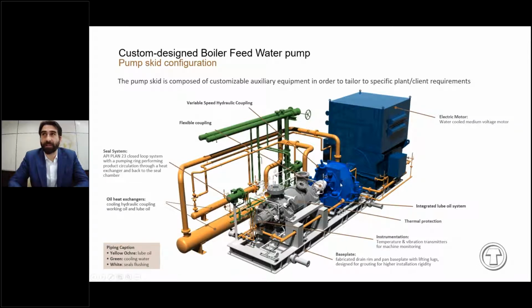It has an integrated lube oil system. You can see in orange color all the pipes of the lubrication circuit. The lubrication oil is used to lubricate the bearings of the pump and the bearings of the electric motor. And all the oil is cooled by two heat exchangers on the left of this slide. One is used to cool the lube oil of the bearings. The other one is used to cool the working oil of the variable speed hydraulic coupling.